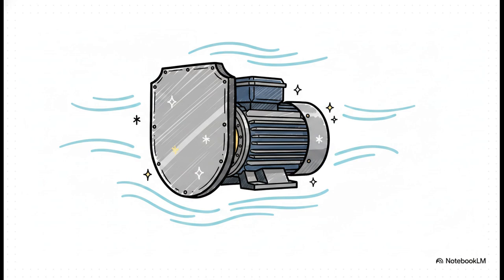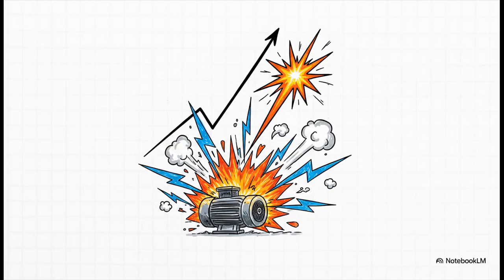Let's contrast our 60 hertz sprinter with the 50 hertz grid, which really acts more like a slow and steady marathon runner. Lower operating speeds on a 50 hertz system mean a lot less mechanical stress. It reduces friction, it puts significantly less wear and tear on the motor's bearings, and it ultimately extends the physical lifespan of all that rotating equipment. So you're essentially trading that 20% performance boost for essential longevity and long-term reliability. Now, here is where we hit what I like to call the rule of unexpected consequences.